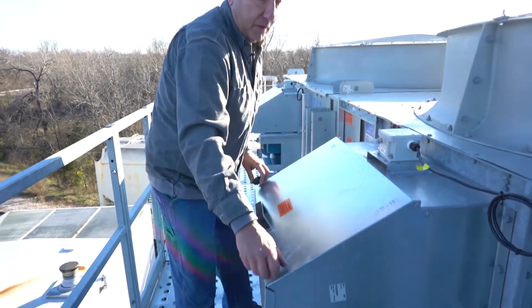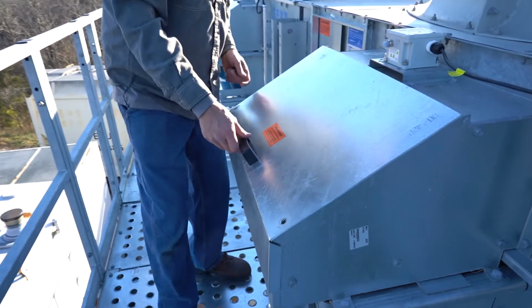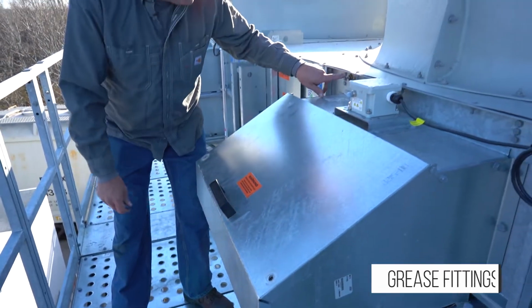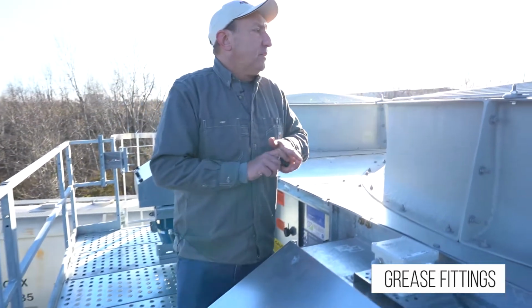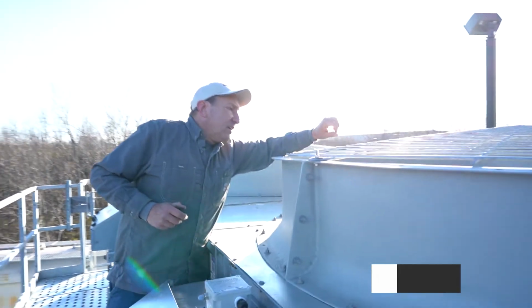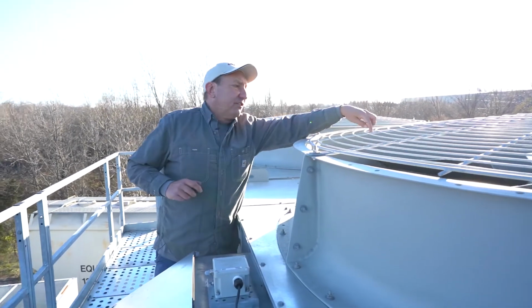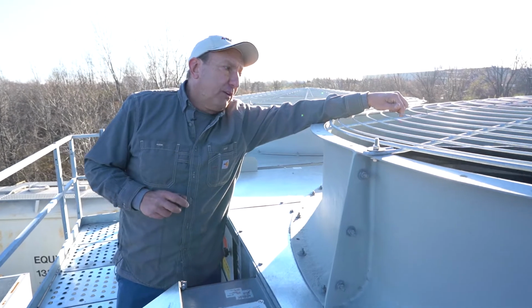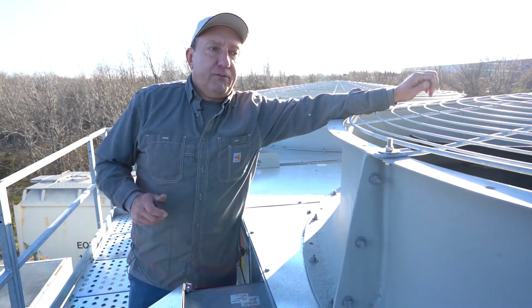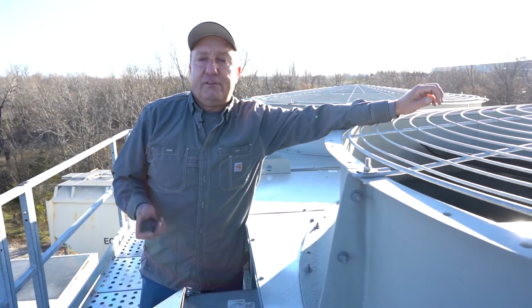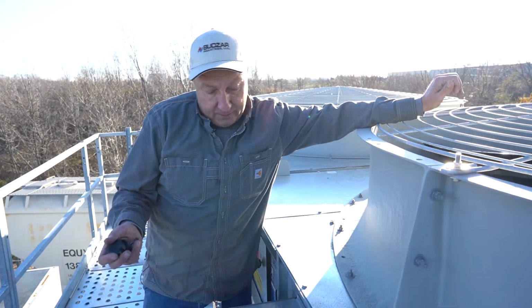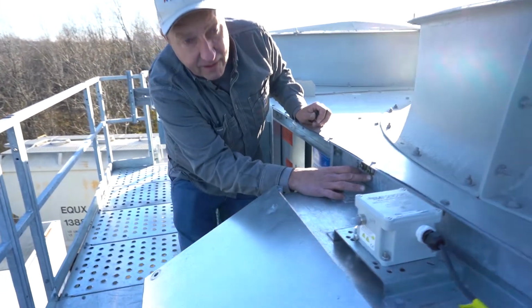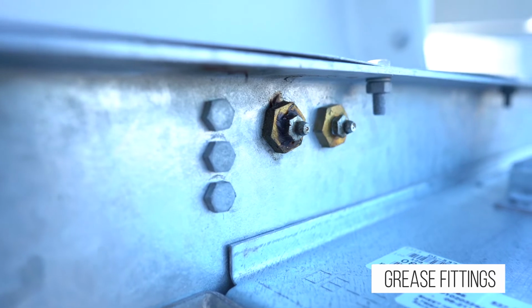Up here, there's a couple maintenance items I need to identify. One is the grease fittings. The cooling fan motor, the sheaves are inside here and they require grease periodically. We'll have to refer to the owner's manual, but I would say every couple months we'd have to grease these fittings. And there's 2 fittings right here.